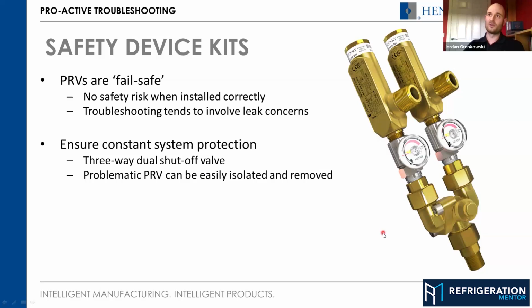Now, Trevor, you mentioned before you're not usually allowed to have a shutoff valve upstream of your PRV, for the simple fact that you could block it off. There is scope in EN 378, the relevant European standard, for a single shutoff valve in line upstream of a PRV. But I think it must be under lock and key, and controlled by certain personnel. But we at Henry don't offer that, because even then, there's still a risk that human error can occur and somebody can forget to turn it on. And so we only offer the three-way valve solution here.